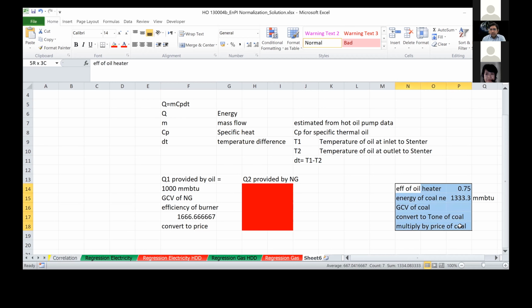Then we need to calculate, backtrack, how much coal would be required to heat up this amount of energy in the oil heater. And for that, we also need to have efficiency. On the other hand, the same amount of energy has to be provided by natural gas. We need to have the efficiency of burners. In this case, we convert it into cubic meters of natural gas and then we multiply it with the price. We can compare both of these together and see which one is better.